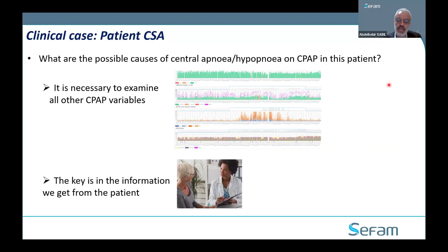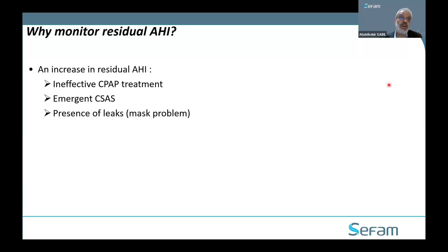Why do I have to monitor residual apnea-hypopnea index? For many reasons. The first one is so simple. It just means that the treatment is ineffective. It could be emergent central sleep apnea. It could be due to the presence of leak, problems with the mask. When patients have a lot of leaks, leaks are going to disturb the sleep. Patients are going to wake up, and patients that wake up a lot through the night, there is a risk of having some central event. The other thing is when the leaks are beyond the threshold of excessive leaks, the algorithms are not reliable anymore, and they can just make mistakes in detecting false events. And that's true with all algorithms for all machines.